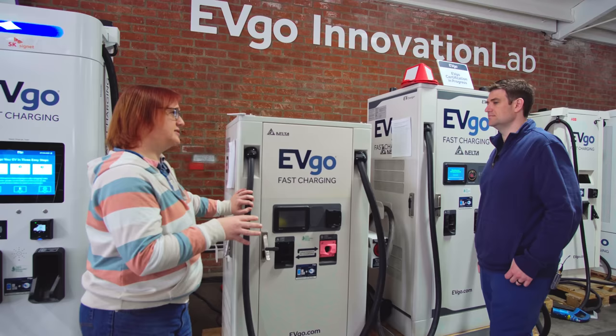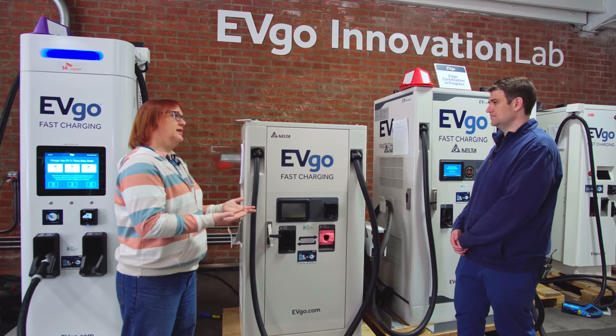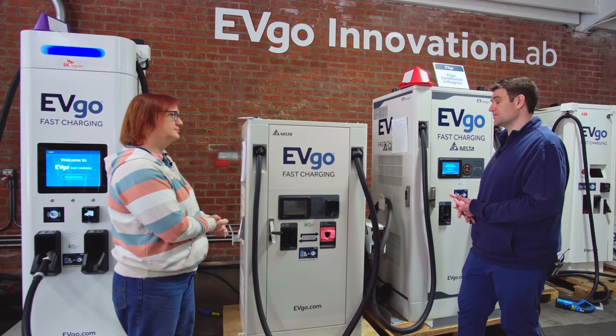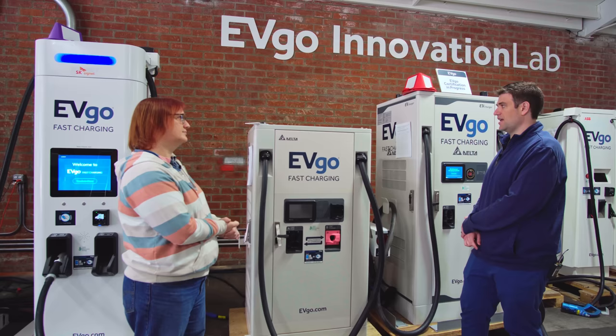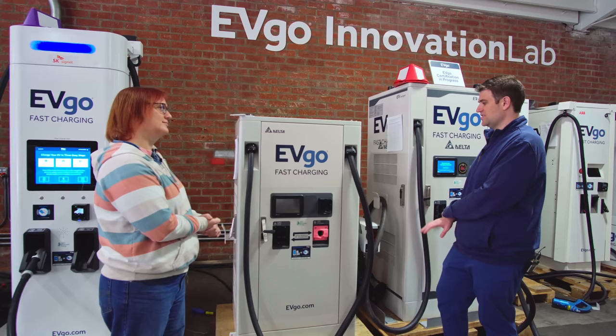It's worth noting that not every location where EVgo puts charging stations is capable of 350 kilowatts. There's a juggling match every provider has to do — you look at the total power capabilities of the location and decide: do we put in two 350 kilowatt chargers, or do we put in eight 50 or 100 kilowatt chargers? Especially in urban environments it can be challenging to get the power we need. These fast-charging depot sites can approach a megawatt, above a megawatt, even three megawatts — which starts to get into territory where a big-box retailer typically has a grid connection of between 500 kilowatts and a megawatt.